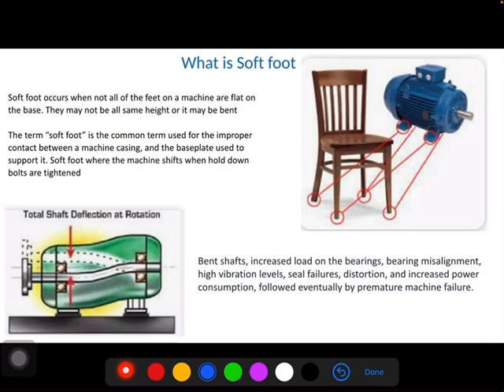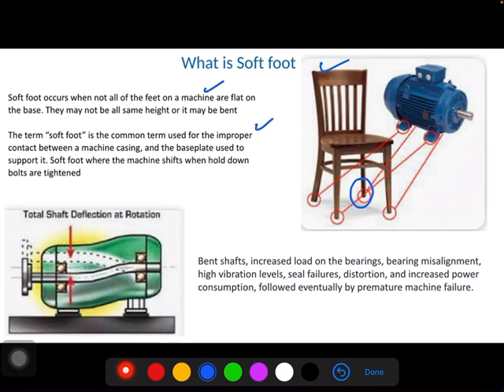First, what is soft foot? Soft foot is nothing but when all the feet on a machine are not flat to the base, there will be a height difference. Because of height difference, there is improper contact between the machine casing and the base plate. You can give an example by considering a chair with a short leg. Due to this short leg, there will be a rocking motion of the chair. Similarly, it happens to the machine.